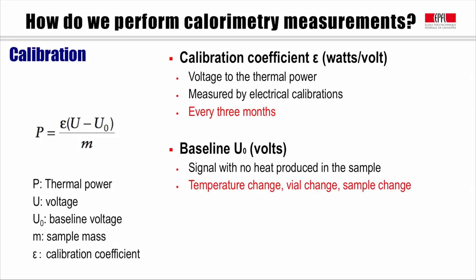Epsilon is measured by electrical calibration. Usually, we do this every three months with the software. U0 is a signal with no heat produced in the sample, but a reference inside. The calibration should be done when we change the temperature, the vial, or samples.